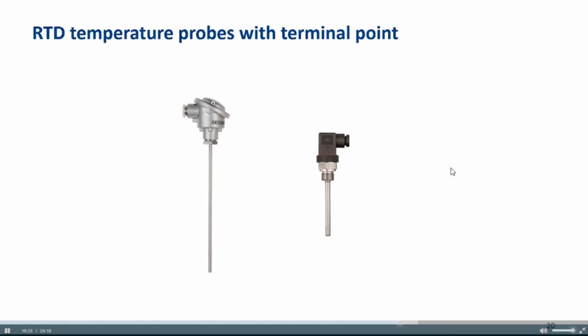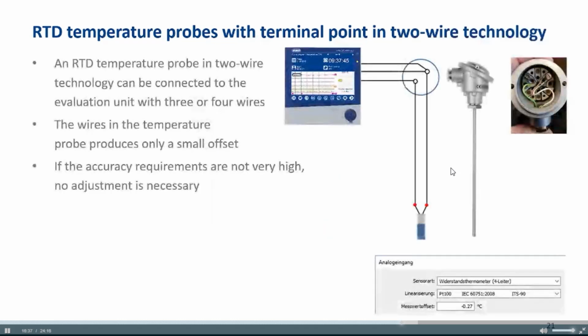I told you in 2-wire technology, you always have this offset. But if you have these probes, you can normally manage this problem. So here you see such a probe, and you see the 2 wires. If you would give the 2 wires over 30 meters to your evaluation unit, maybe you would have an offset of 5 Kelvin, whatever, if you work with a PT100, for instance. So please don't do this.